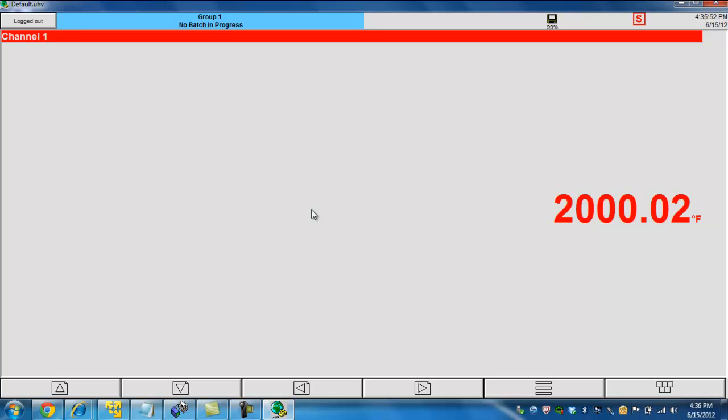And at 2,000 degrees, we're probably going to see the biggest amount of offset here. With any kind of instrument out there, the linearization error obviously increases based on the scale of the input. So had we gone from 0 to 1,000 degrees and that was our full scale, the accuracy would be better than 0 to 2,000 degrees. So even though we are going 0 to 2,000 degrees, which is for the most part the majority of the scale for the thermocouple, we're still reading relatively accurate readings at 2,000 degrees, no more than 0.4 degrees off.